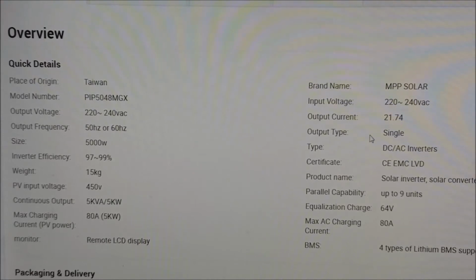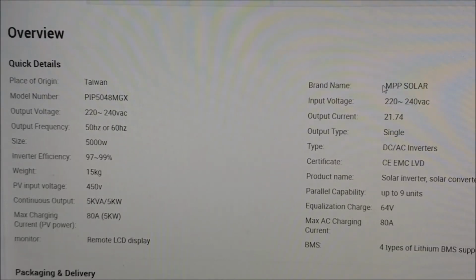Parallel capability, that's an important thing. This allows you to put 9 inverters all parallel to each other. So that would be 189 amps, you're talking 200 amp service with that. And if you're going for a lot of amps, you're looking for a brand like MPP or Growatt, one of the ones in this price range. They're not the cheapest out there, but they're not the $7,000 ones either.